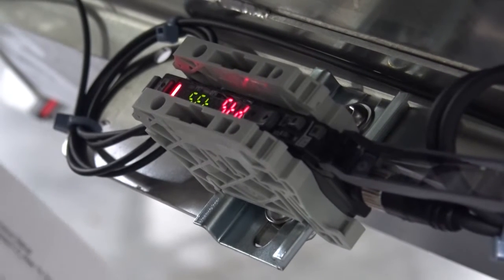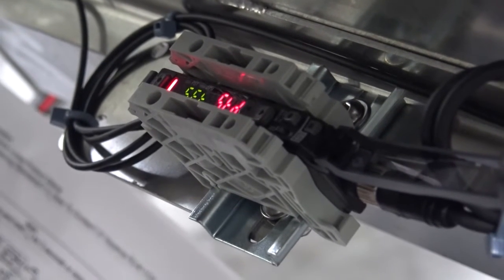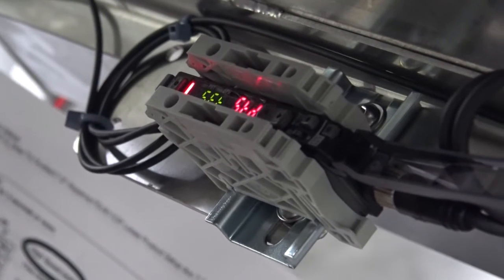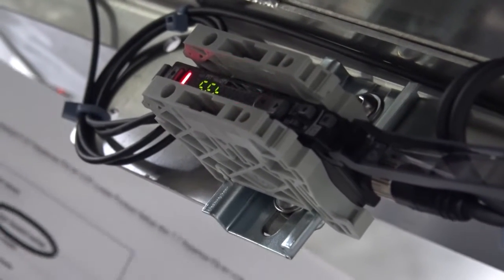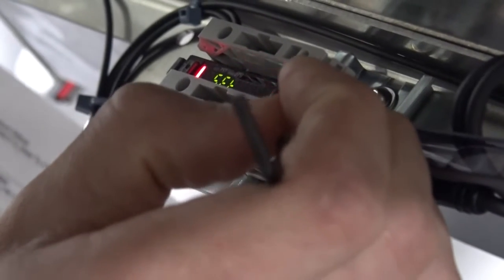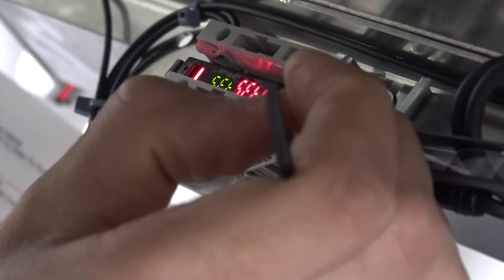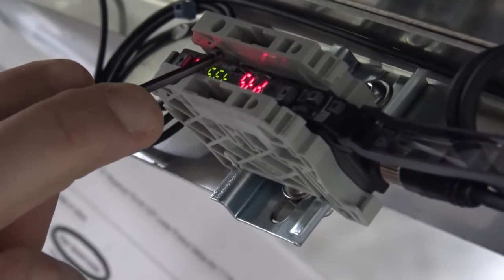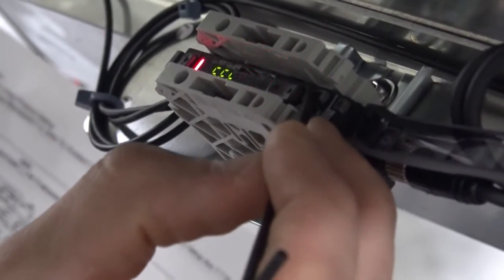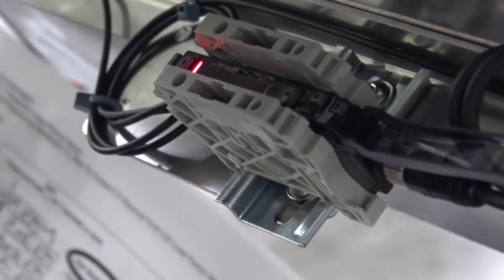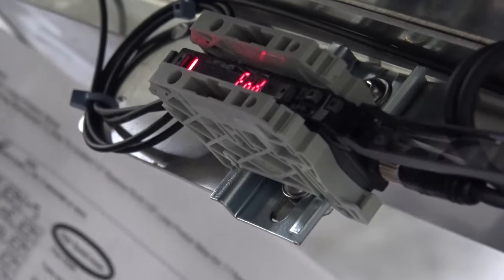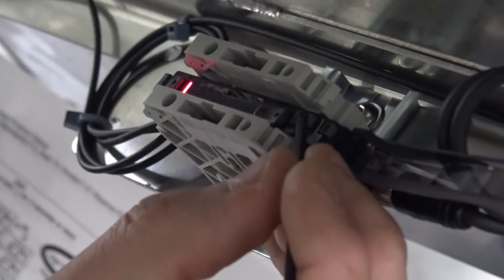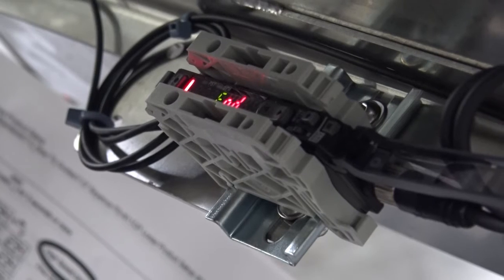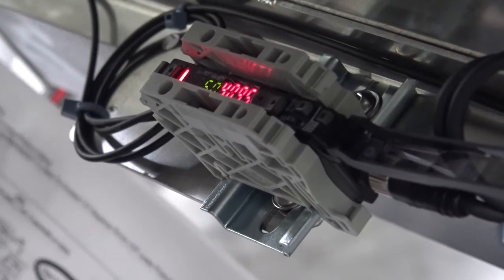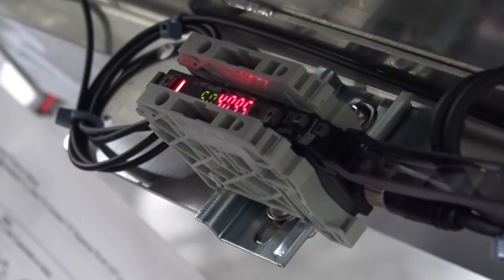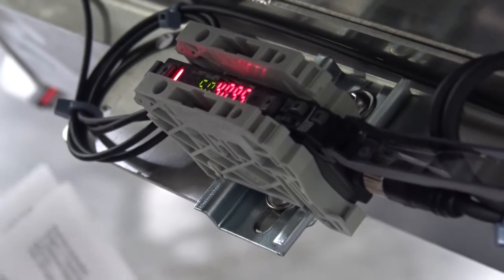Okay, and then my next subcategory is going to be, let's see here, I want to set the normal sensitivity method. You're going to see blinking STD. I think that represents standard. I can navigate left and right, but I do want that STD. So I'm back on the STD, and I want to hit mode again to enter the standard mode. Okay, and then end function. I can navigate to some other functions, but I do want end to accept the normal sensitivity setting. So now I'm on high speed mode, which is the right mode for this application.